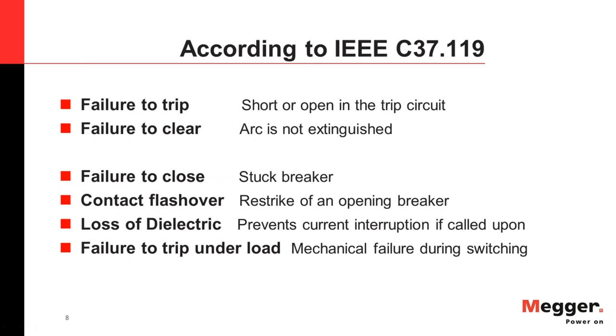Starting with what is Breaker Failure. According to IEEE C37.119, which is a standard for Breaker Failure Protection, they have categorized Breaker Failure into these categories. The first two — Failure to Trip and Failure to Clear — are called Breaker Failure. The rest can lead to a Breaker Failure, but they are not categorized exactly as Breaker Failure.